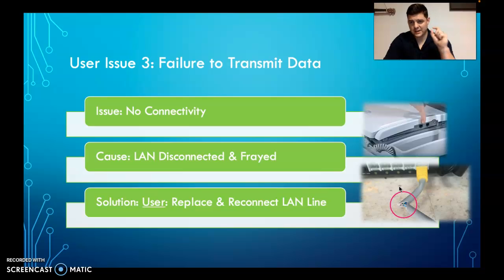And so the LED lights within the unit's display should be starting to blink and flash, and then eventually you're going to want to see that green light pop up, and the activity light should be flashing yellow, saying that stuff is being transmitted. And again, if you get another error message popping up, then we'll know there may be an issue there. But the verification of that would be to just connect the LAN line, let the system do its job, let it run a self-check, and in this case, it does. The connectivity goes through, and they're able to resubmit the data. So it's just a reattempt, and it passes through.